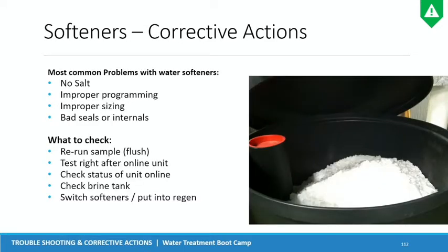Softeners, things that go wrong with water softeners, right? Most common things, no salt. Seems like a no-brainer, but how many times you're the guy who adds salt, you go on vacation, I come in, the softener's hard, and I immediately open the brine tank. It's like, oh, well, John's not here, and that's John's job, right? He's the only guy who adds salt into our softener. So that's important to make sure that we don't run out of salt.